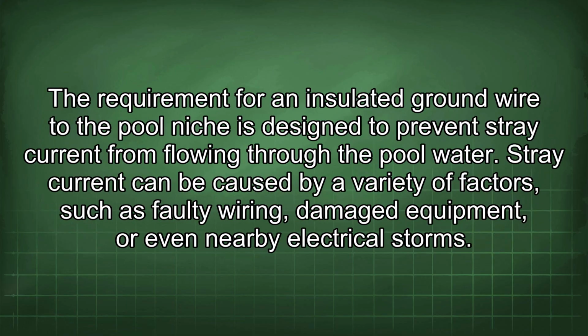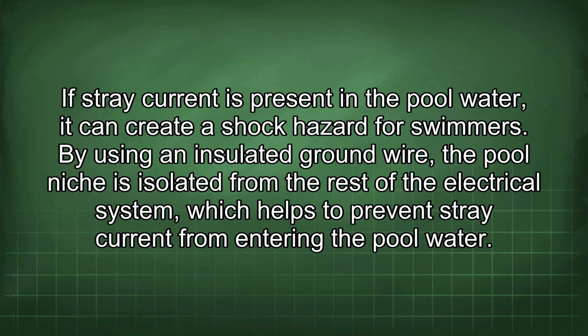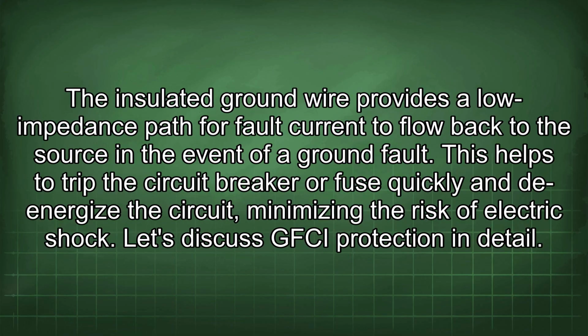The requirement for an insulated ground wire to the pool niche is designed to prevent stray current from flowing through the pool water. Stray current can be caused by a variety of factors, such as faulty wiring, damaged equipment, or even nearby electrical storms. If stray current is present in the pool water, it can create a shock hazard for swimmers. By using an insulated ground wire, the pool niche is isolated from the rest of the electrical system, which helps to prevent stray current from entering the pool water. The insulated ground wire provides a low impedance path for fault current to flow back to the source in the event of a ground fault. This helps to trip the circuit breaker or fuse quickly and de-energize the circuit, minimizing the risk of electric shock.